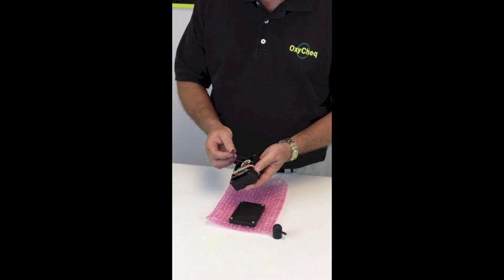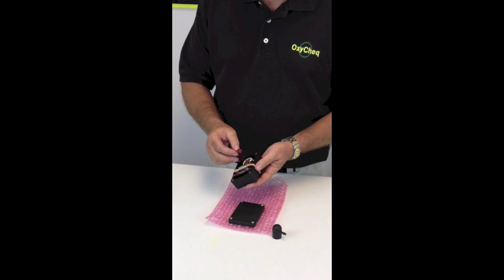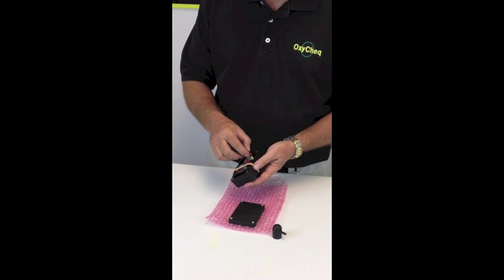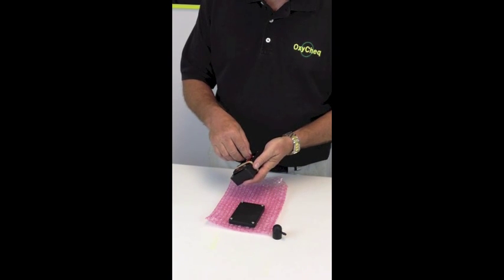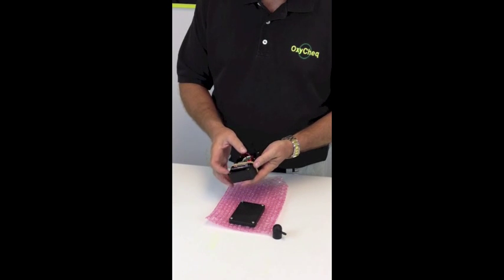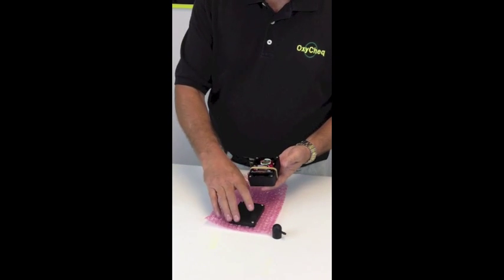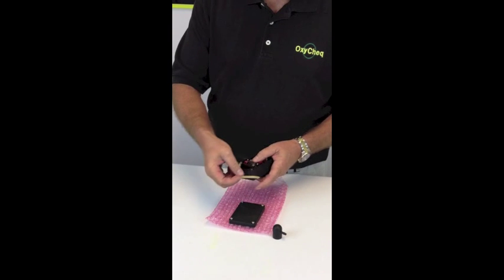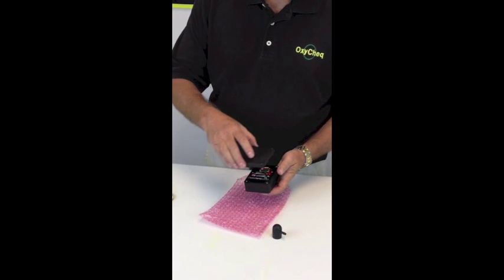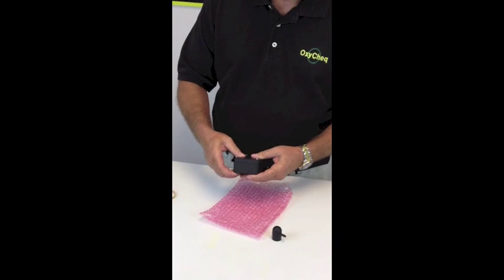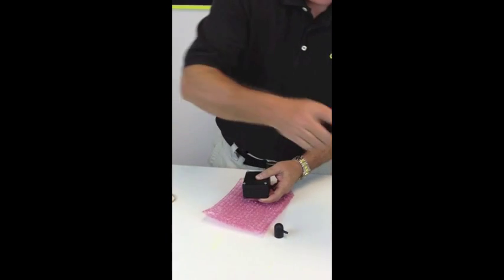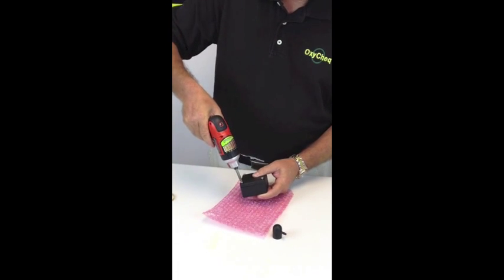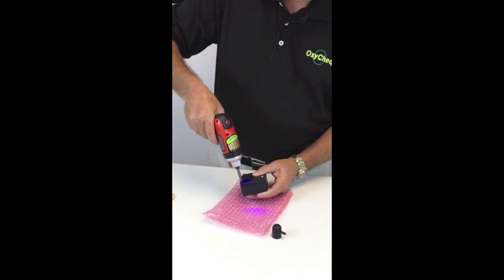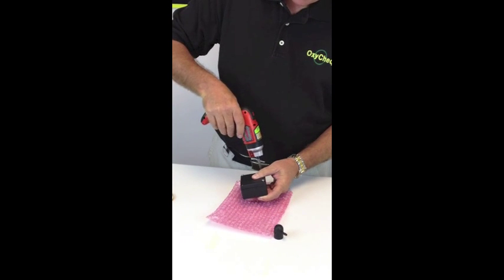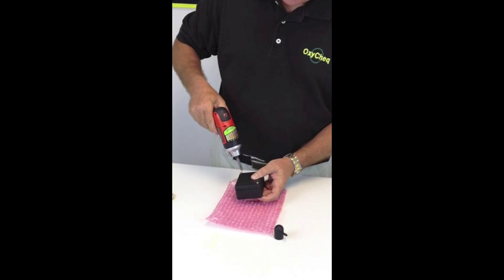Once you're done, now we're going to take the Molex connector off of the sensor and we're going to place it in the Molex block on the analyzer itself. And there's a little locking device there to keep that in place. Once that's done, we've removed the rubber band, and now we can put the back of the analyzer back on the case. We'll screw in the 4 screws using a Phillips number 2 screwdriver.